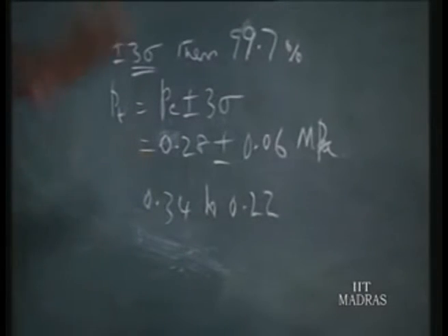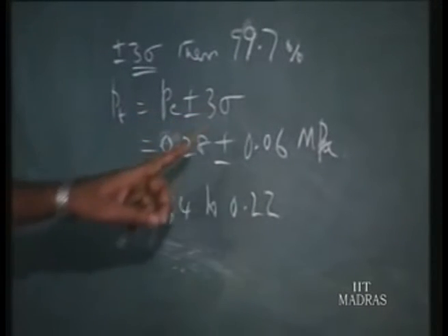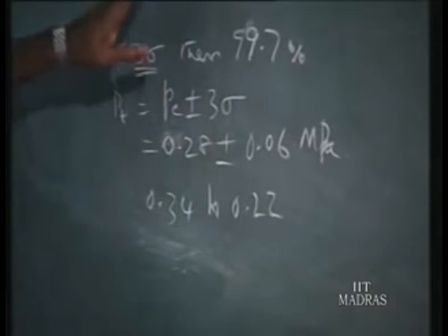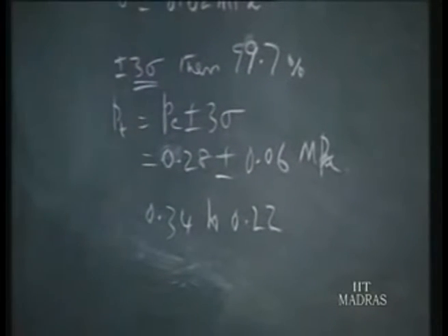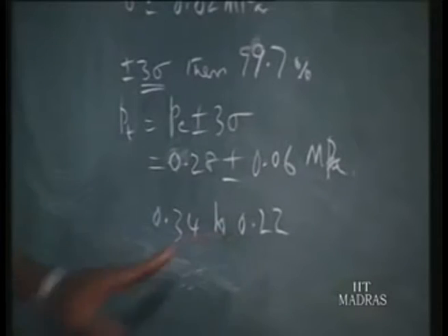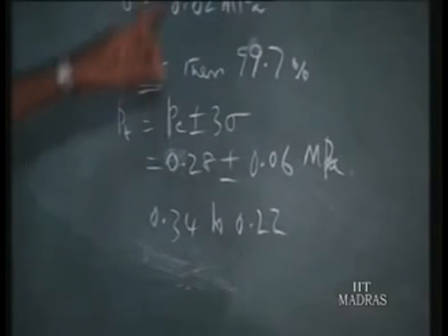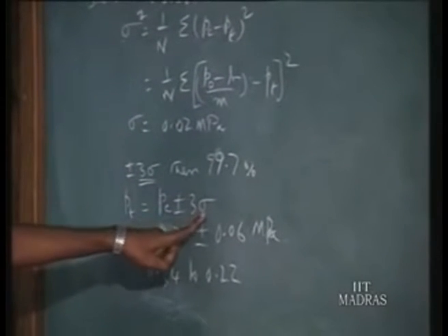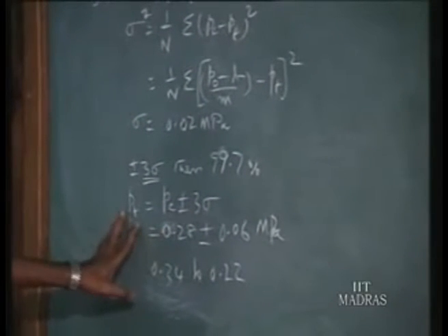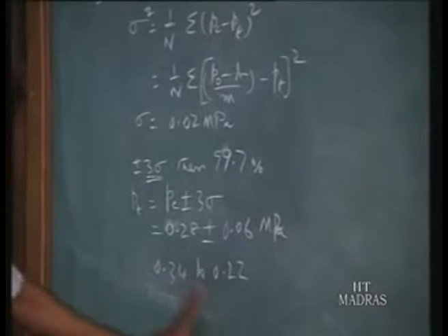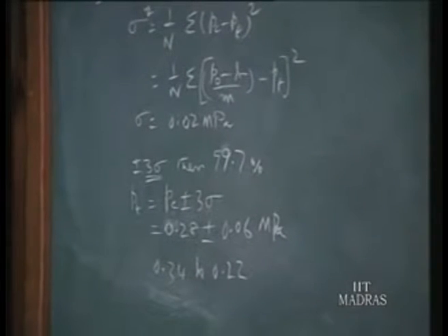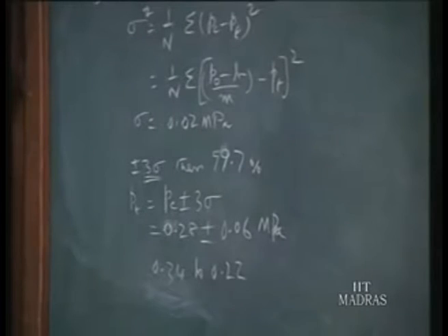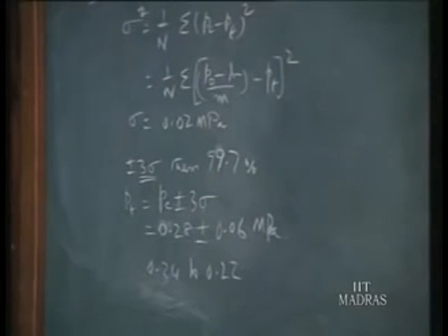After recalibrating the pressure gauge, we can now specify the new accuracy of the instrument like this. The corrected value should be found by using this equation. That corrected value with the 3 sigma limit then gives the true value. The true value, as always, has a range within the 3 sigma limit. So that is our recalibration. For a given reading, what should be the correct reading and its uncertainty. That is what we have found out now.